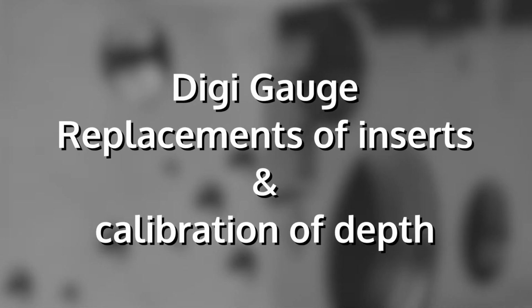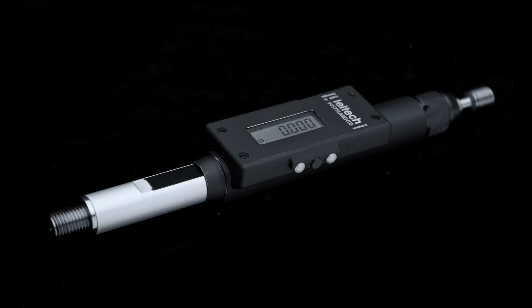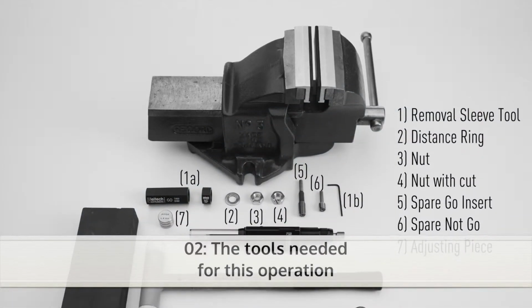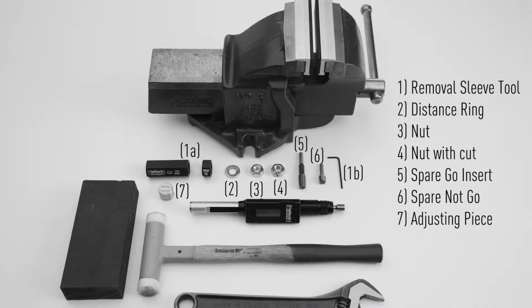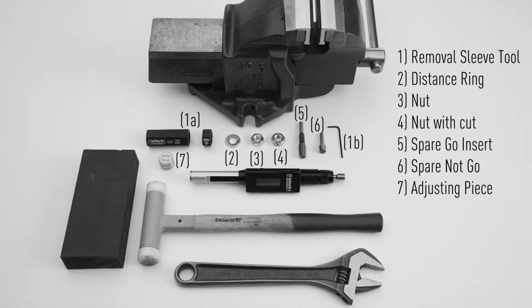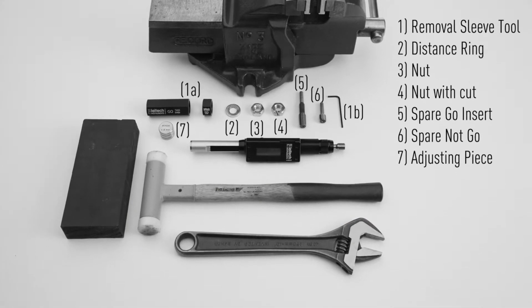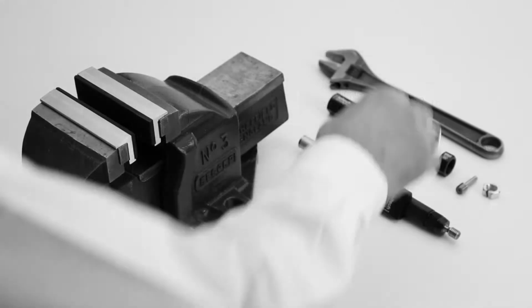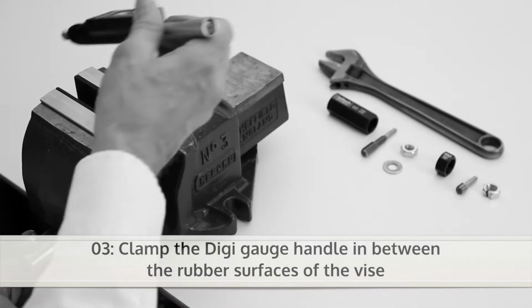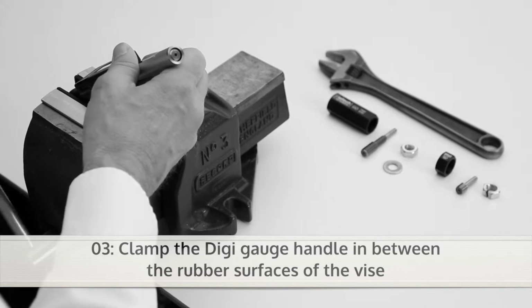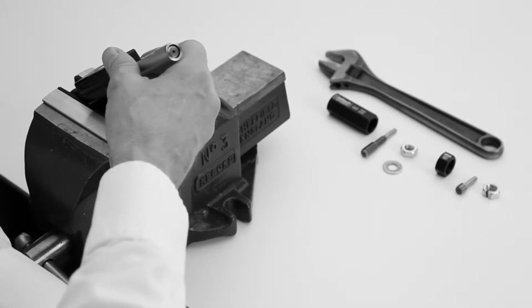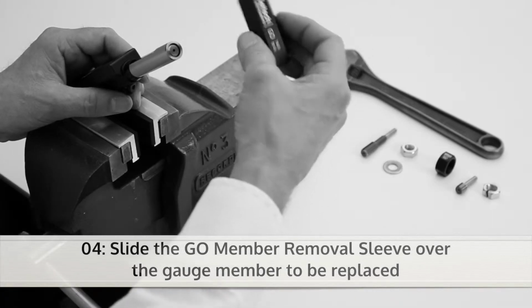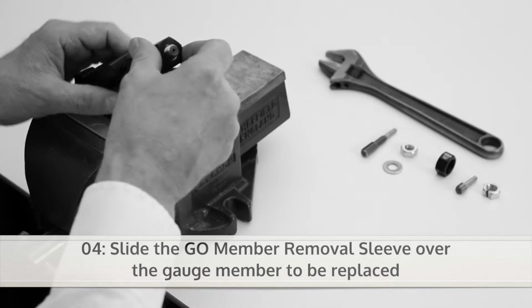Welcome to this introduction on how to replace the inserts in a Litec DigiGauge and how to perform a calibration of depth. You will need this set of tools for the operation. Tighten the vise so the DigiGauge will stay fixed between the rubber surfaces of the vise. Now slide the Go member removal sleeve over the gauge member to be replaced.